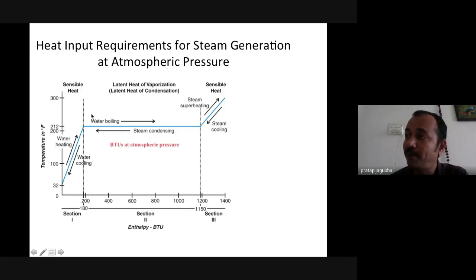So the property of the steam is utilized to heat in any process industry, for heating applications like jacket heating and indirect heating in heat exchangers, in pharma and chemical industries. When the water is getting heated, the sensible heat is available at 100 degrees, and then at 100 degrees it vaporizes in the form of steam.